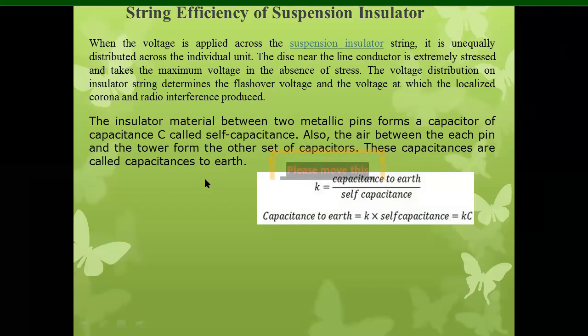So the lowermost disc of the suspension insulator comes under tremendous voltage stress. That's why there is a possibility of rupture of the disc of that suspension insulator. So we have to distribute the voltage uniformly across the whole string of the suspension insulator. In order to do that, we have to use some methods, that is, methods of improving the string efficiency. First we will see what is meant by string efficiency. Afterwards we will see the various methods of improving the string efficiency, and then the numericals on the string efficiency, that is, how to calculate the string efficiency.